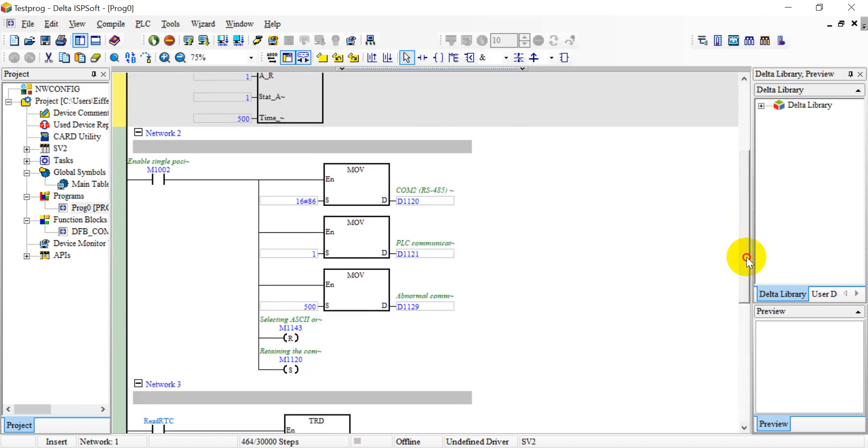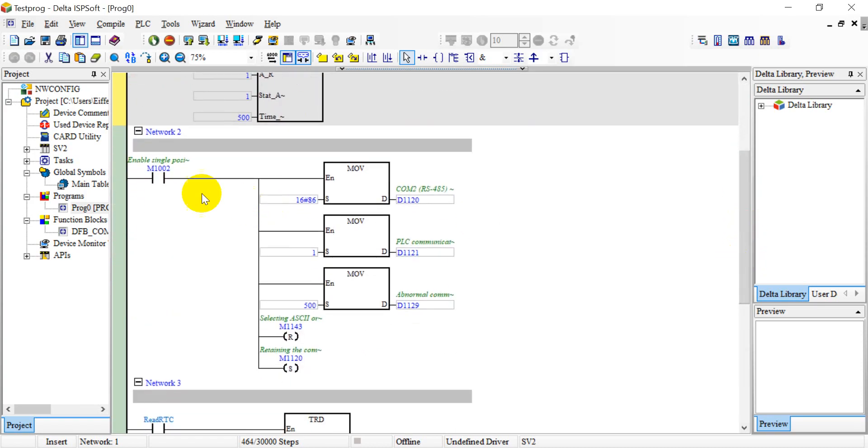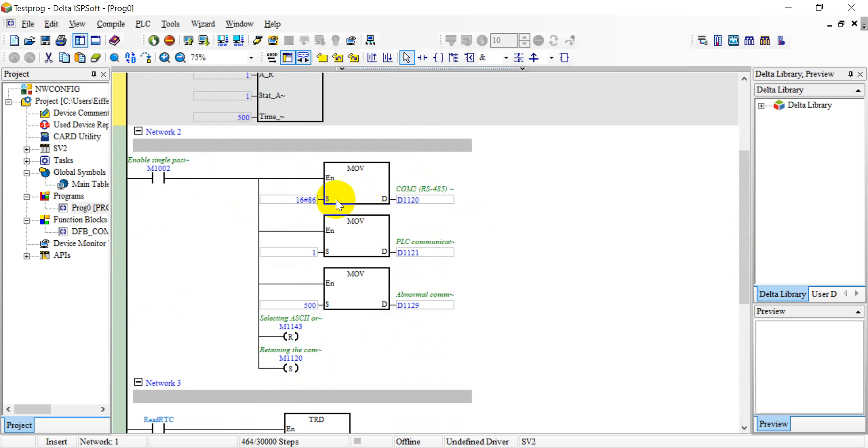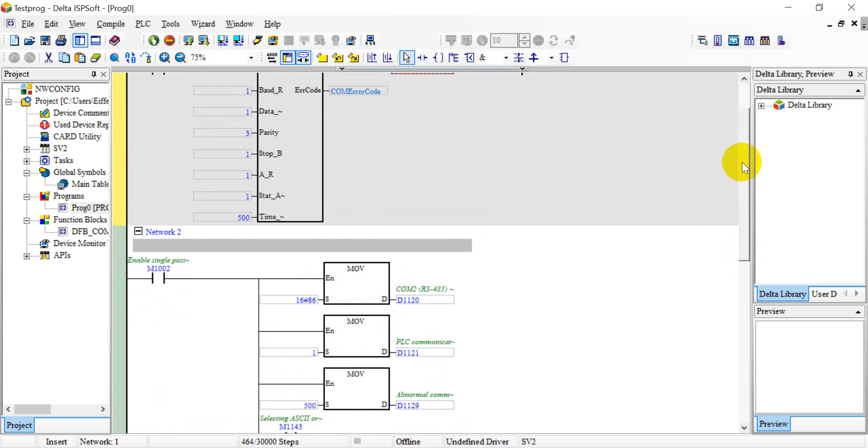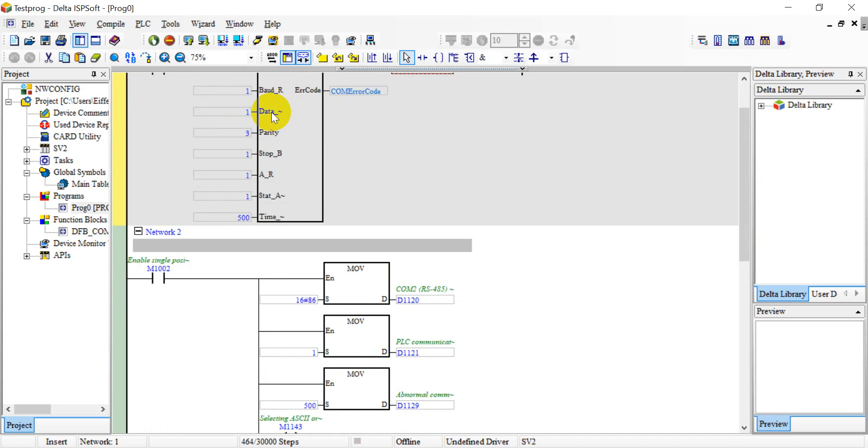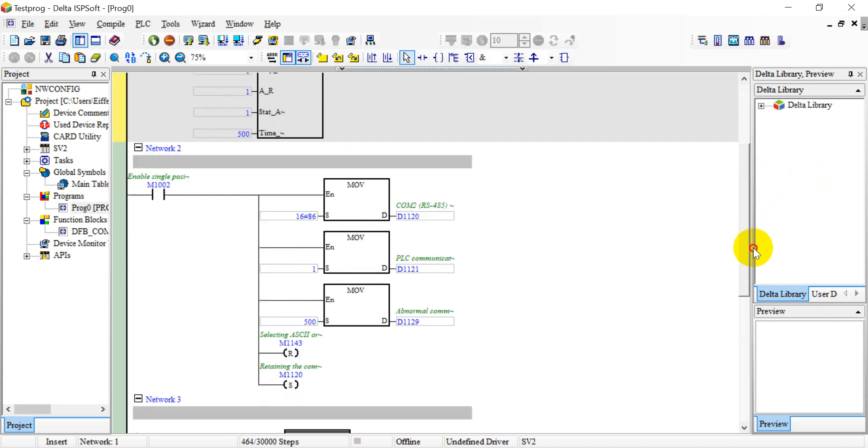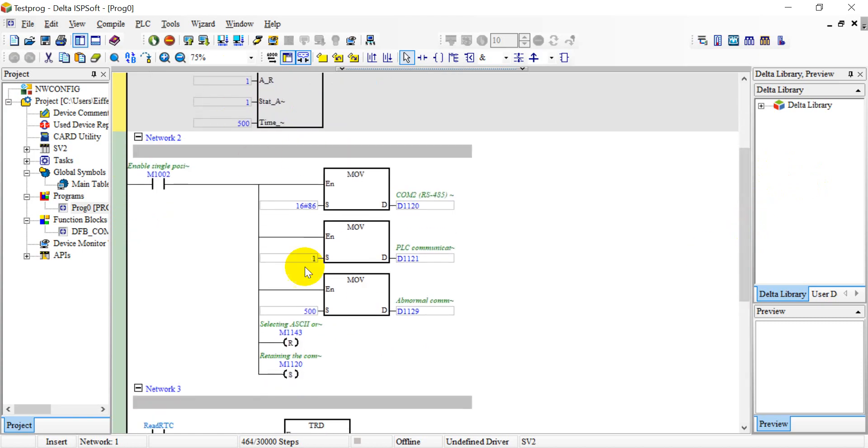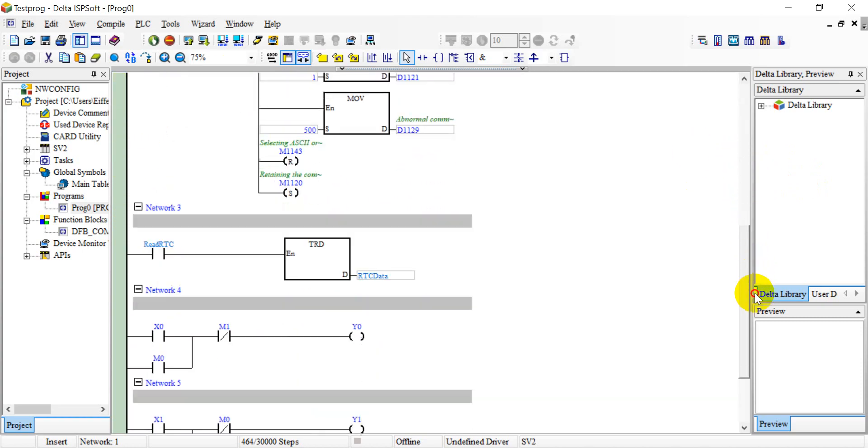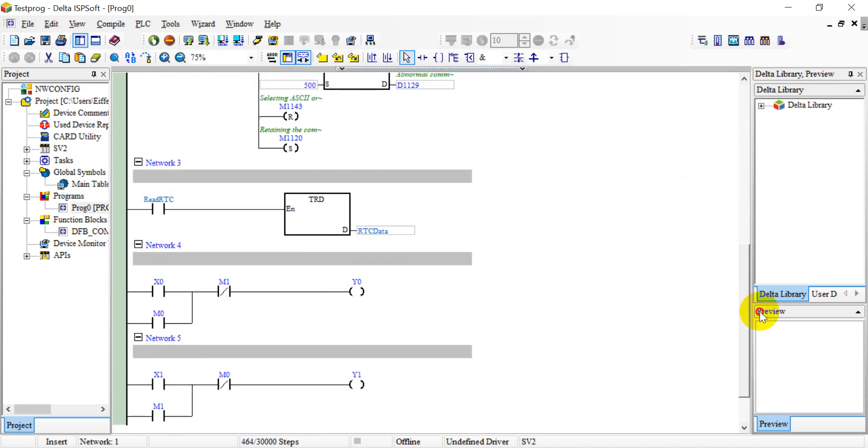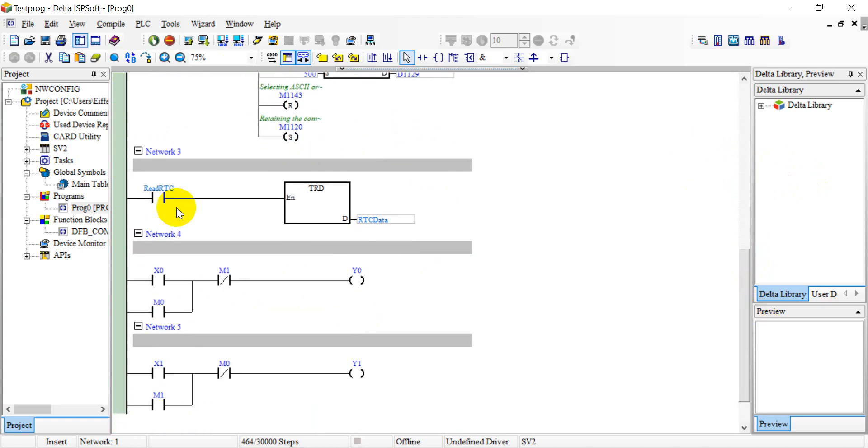Second part is we can define the space according to the communication protocol with special register and flag. This one we define the baud rate, data bits, parity check, stop bits, ASCII, RTU, etc. So these two are basically the same. And then we give some standard ladders.